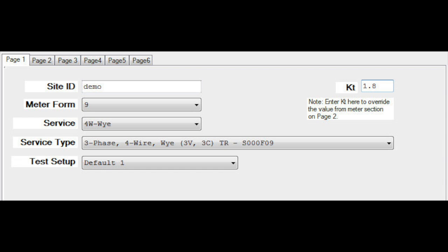To test this site effectively, you only need to fill out these fields. Create a site ID, select your meter form — in this case it's a 9 — select your service, in this case 4-wire wye, your service type: three-phase, 4-wire, wye, three voltage, three current transformers. Then select a test setup — either create one or select one you've already created — and enter your K sub T. Be sure and save this, then select this site. At that point, you should be ready to begin your testing of the form.